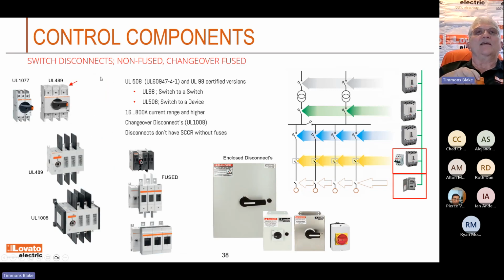Disconnects. Now we're dealing with UL 98 or UL 508. And be aware, when you see this UL 60947 standard, that was a harmonization done, I think, around 2018, 2019 with the UL 508. So it's all UL good. Okay. So the UL 508 is a switch to the device, and the UL 98 is from a switch to a switch. Okay, and you can kind of see in the 489, it's got those fins on it again. You see them big black fins there, all of them. Now you'll see here in the bottom left, you've got a UL 1008. That's for changeover switches. Okay, so if you're coming in from one power source or another, you're trying to come out to feed a distribution, then we have this UL 1008.